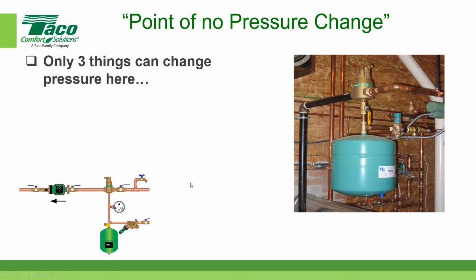Now, let's not forget another very important thing here. We call this the point of no pressure change. So there are 3 things that can change the pressure. And let me go back up just a little bit. What I'm talking about is this point right here. Notice where the expansion tank is meeting the system. That's shown here and here, but this picture doesn't show a gauge where a gauge should be. A gauge should be right here, as I've shown it here. We want that pressure gauge to be as close to the point of no pressure change as possible.